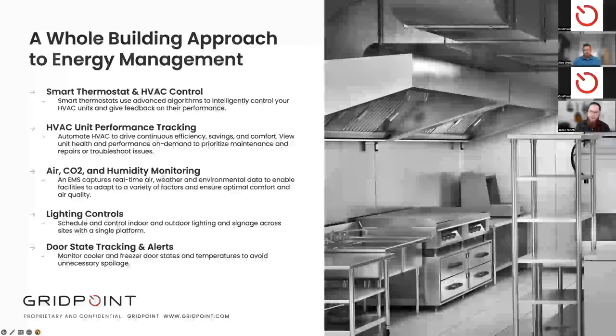Another piece of that is HVAC unit performance tracking. The energy management system collects all the data measured on site. With a smart thermostat and HVAC control, you have the thermostat itself, and you may have a zone sensor that's separate. If the thermostat's back in the manager's office, for example, and you have a unit that services a dining room out in the front of the store, you could have a zone sensor, and you'll have a duct sensor to measure the temperature of air coming out of the supply.